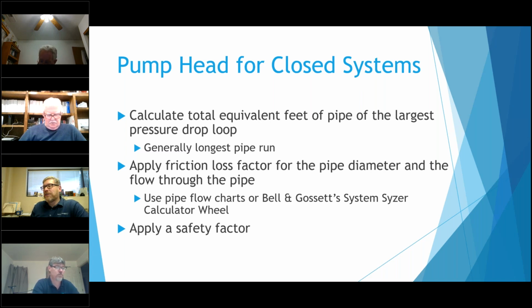You're not really adding that much. But in some of the larger systems where you've got 50, 60, maybe even 80 feet of pressure drop that you're trying to overcome, 10% or 15% is really plenty, because it obviously changes it quite a bit.